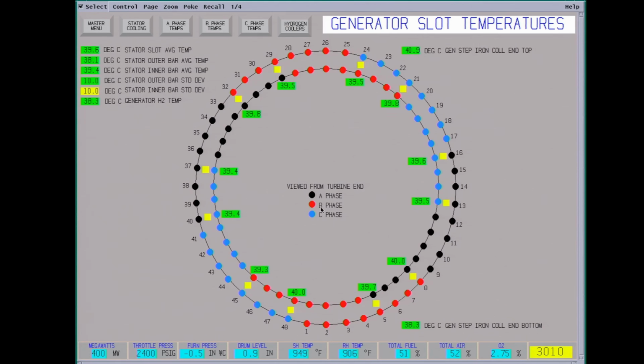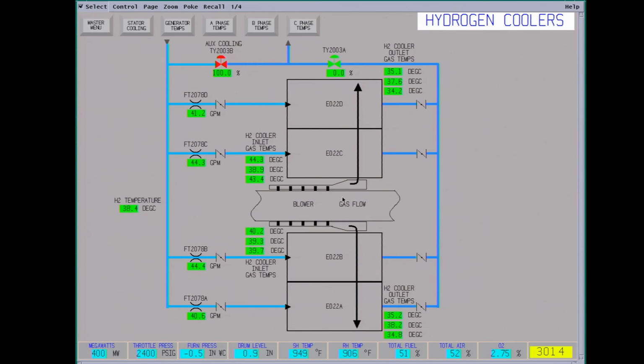Another screen just showing the generator temps. Got your A phase, B phase, C phases, stator slot temperatures, generator hydrogen temperature. This is your hydrogen cooler. This is inside the unit. These are the hydrogen coolers actually inside the generator. They sit on each end. There's a blower on the end of the shaft that moves the hydrogen gas through your heat exchangers. It picks up a lot of the heat.